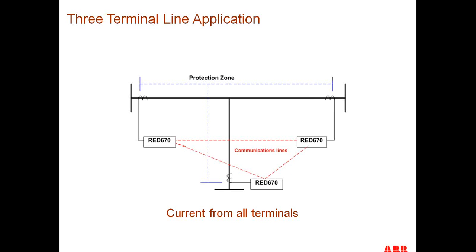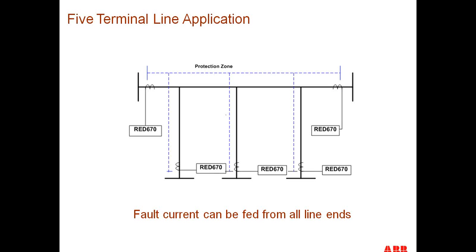They all make their decisions independent of each other. You can have, with modern microprocessor relays, up to a five-terminal line. So we can have 3 taps on the line plus the normal line end. I'm not saying your planner should plan for a 5-terminal line. That would be something I wouldn't want to deal with either, but you can get multiple communications modules in each one of these relays to support something like a 5-terminal line.